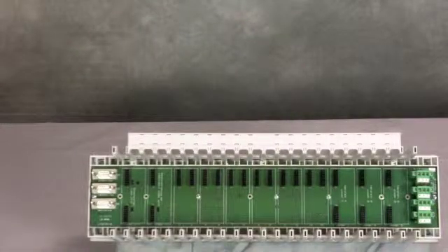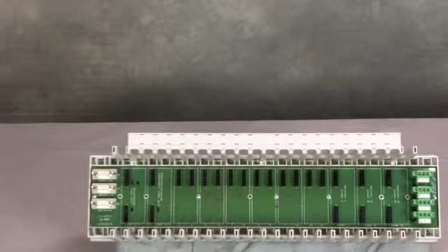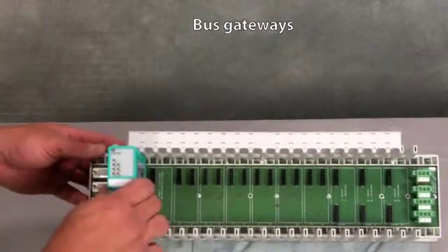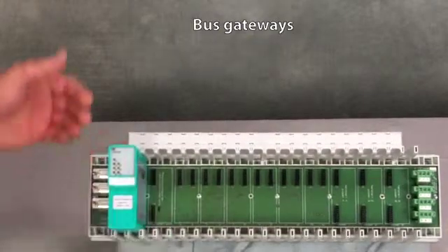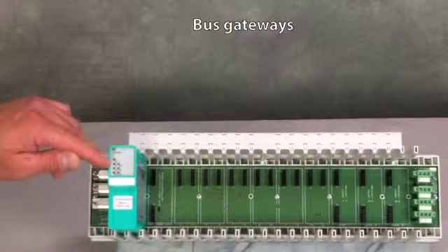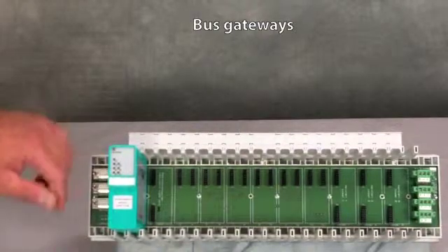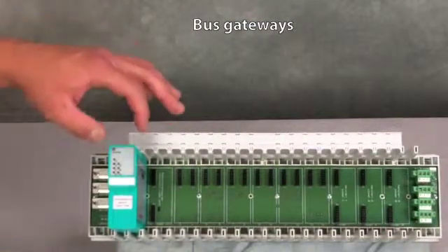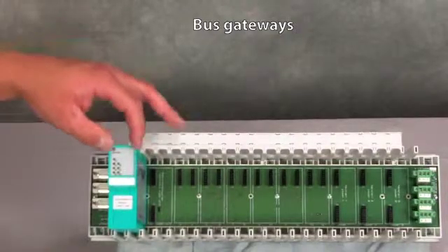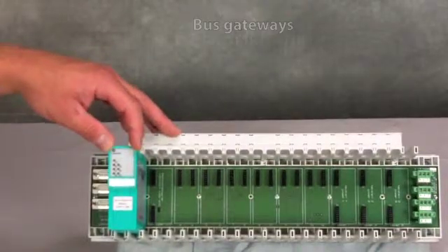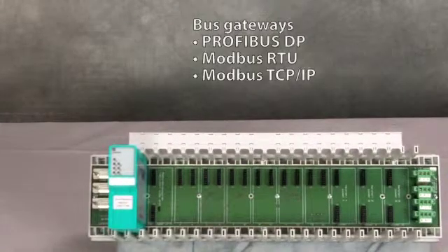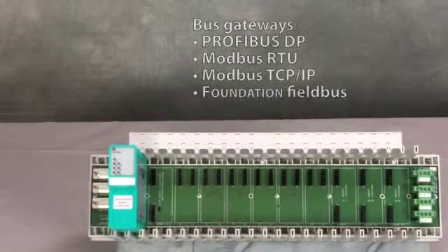The first item that you're going to choose once you've got your backplane is going to be your bus gateway or bus coupler. So in this case we have a PROFIBUS gateway and you can see all of the modules have LED indications and they're simple plug and play hot swappable modules. The different bus gateways that we have are PROFIBUS, Modbus RTU, Modbus TCP IP and Foundation Fieldbus.